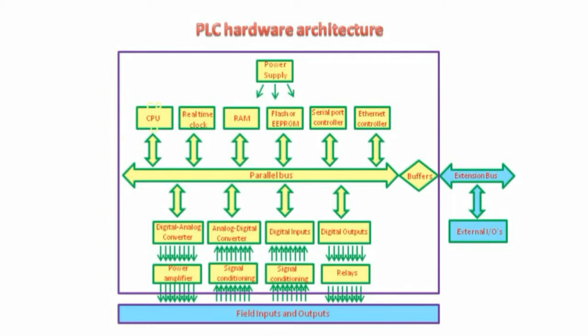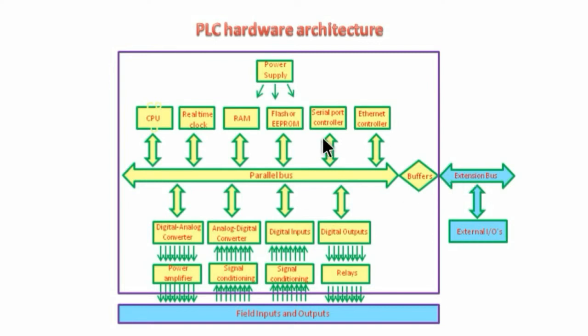Let's talk briefly about the PLC hardware architecture. It consists of the CPU, real-time clock, RAM and flash memory or EEPROM, a serial port controller for RS-485 and RS-232 connections, and an Ethernet controller. Of course, there are also the input-output modules. A parallel bus connects all the modules together, and extension buses are required if extra IOs need to be connected to the PLC. And of course, the power supply to power all the modules.